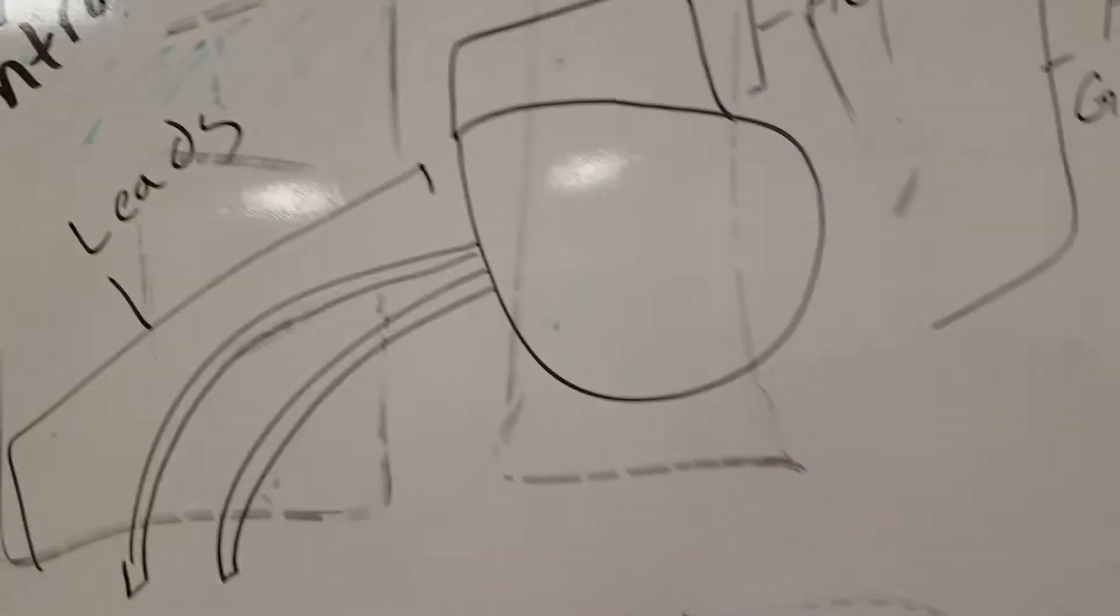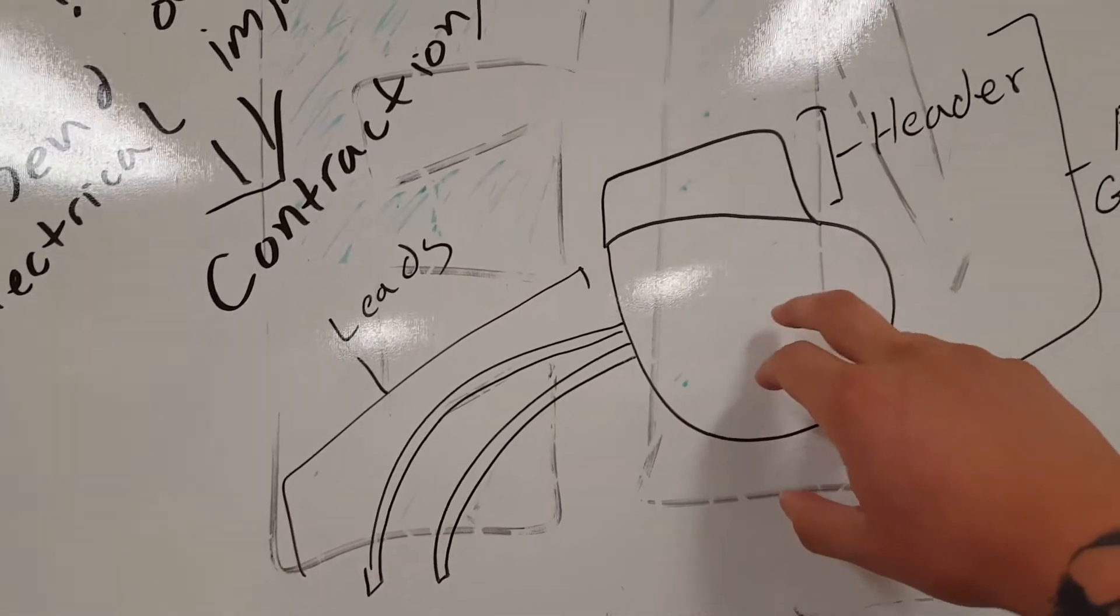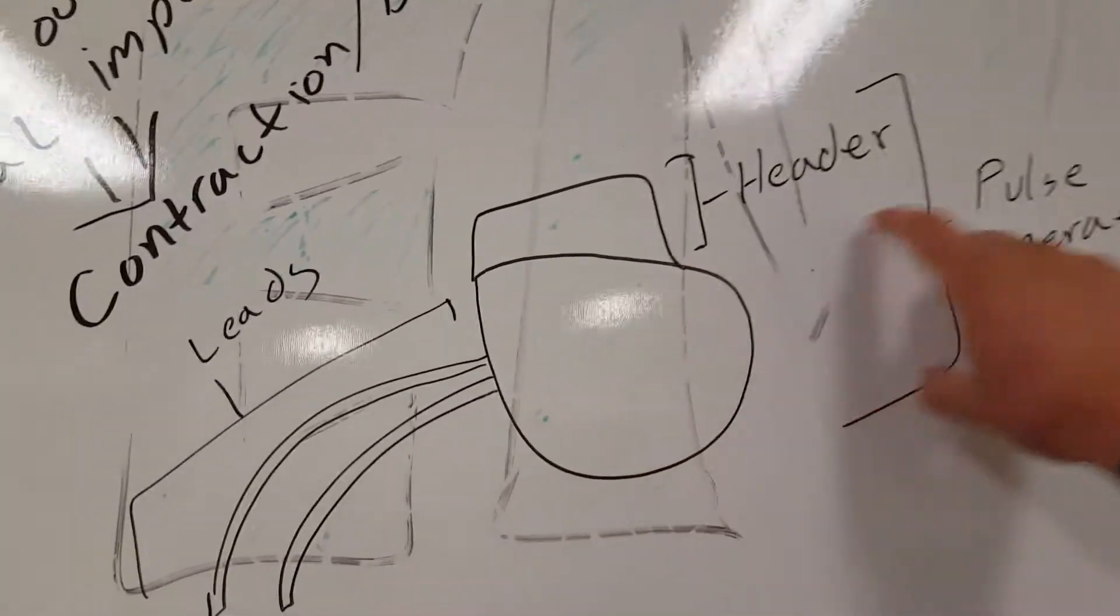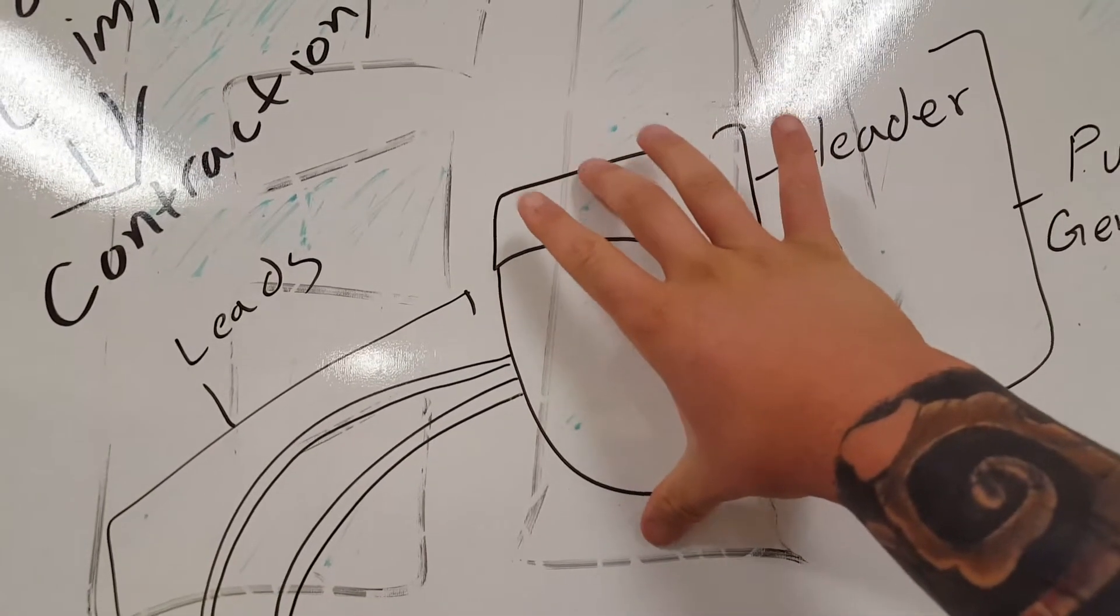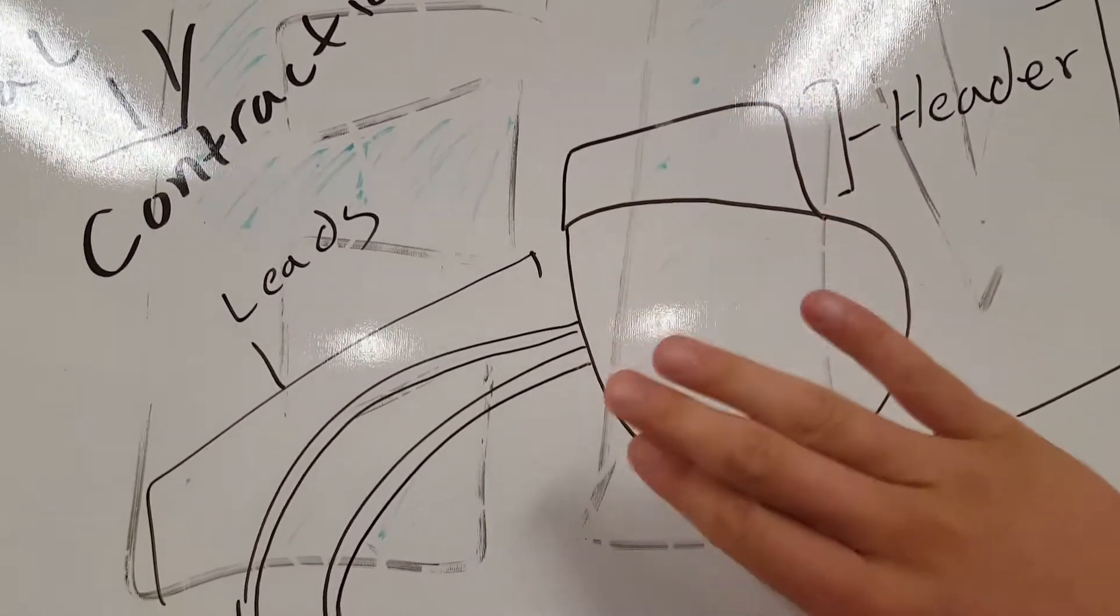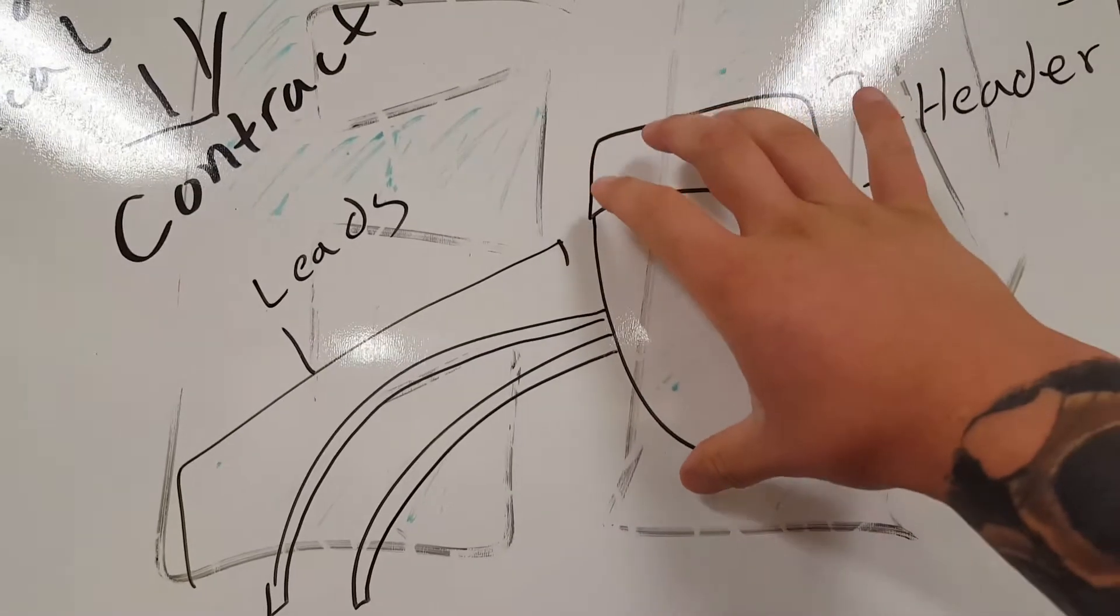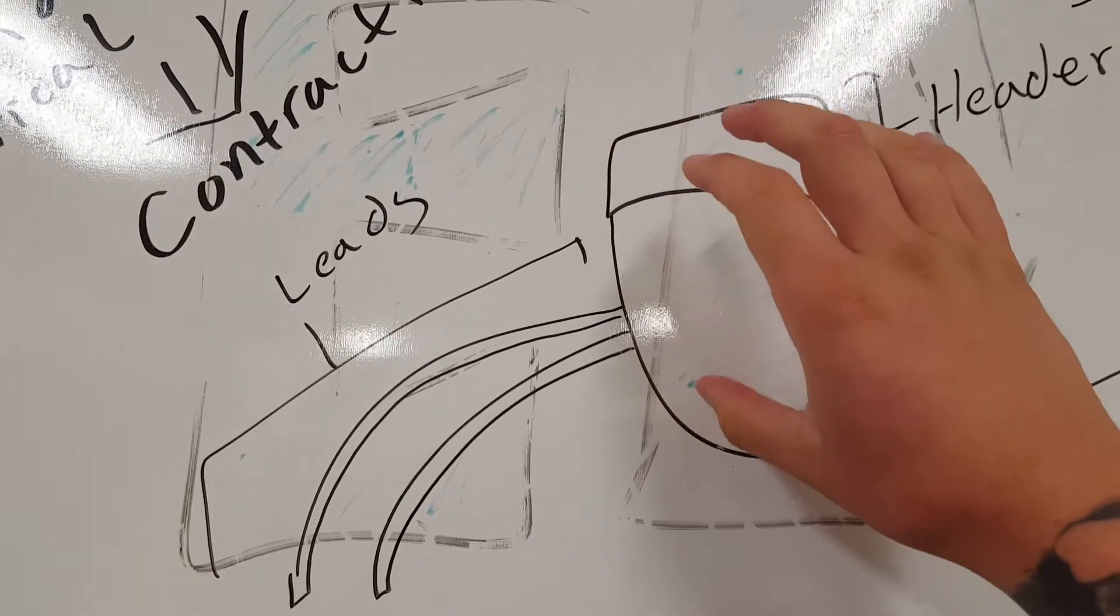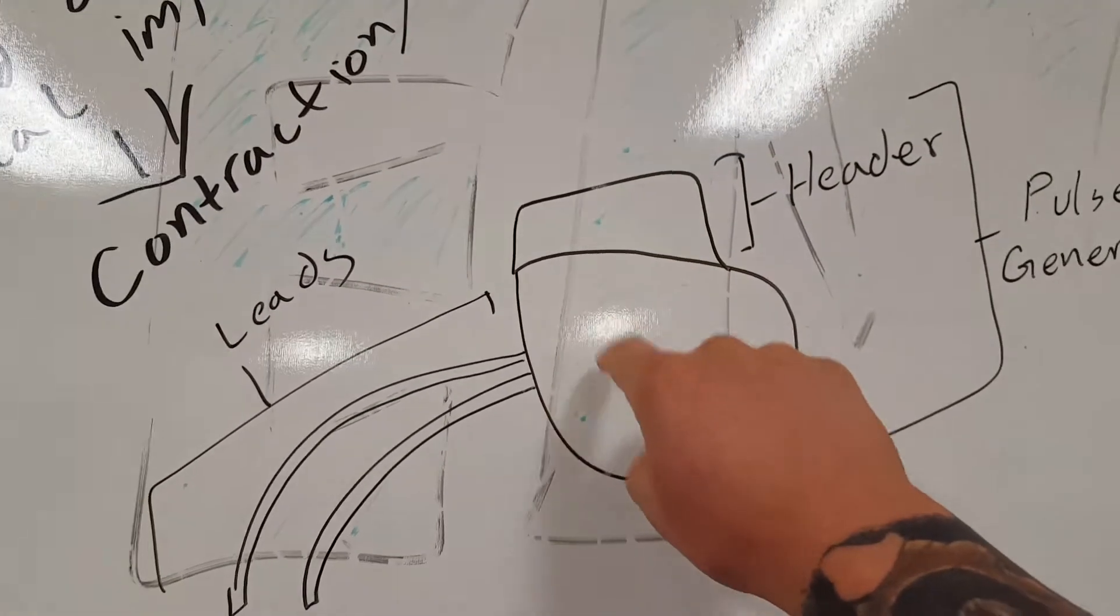So a pacemaker - this is a general drawing of a pacemaker. So you have what's called the can or the pulse generator, which is the entire circuit. This is where the circuit and the battery are. When you see that little bulge on your patient on the chest, this is what you're looking at. For the most part, this will be bulging out of your patient's chest. This is the actual pacemaker itself.